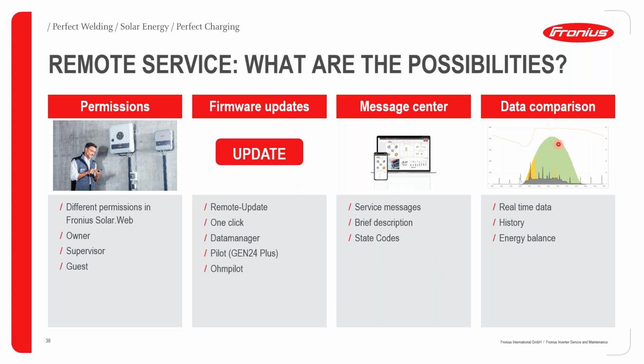Also importantly, you can do data comparison. If you have a system with several inverters connected, SOLAR.WEB allows you to have an overview of each inverter's performance. If you realize that one inverter is lagging behind the performance of other similar inverters, this can mean that something needs to be done on site. This is very valuable because you're able to identify this kind of situation even before making a planned trip to site.